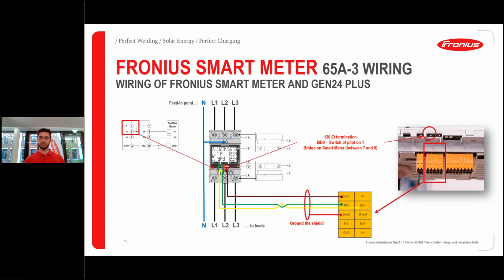And on the Gen24 Plus inverter, we also have a way to terminate it. This is with this little dip switch on top, which we just put into position 1, which is the on position, and then we have both ends of this communication line terminated, and we ensure the highest data communication without any losses. So these are actually the most important things to remember when it comes to data communication and the Fronius smart meter.